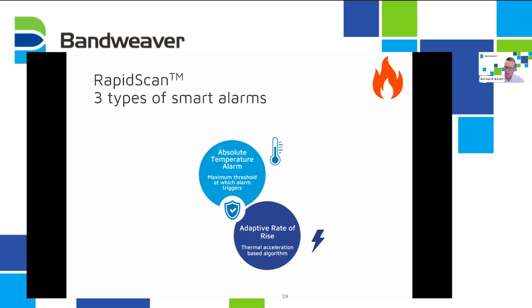We have our adaptive rate of rise. Other systems do use rate of rise. Ours, as we'll look into, looks at the baseline. It has an algorithm that looks at the change in the thermal situation and responds accordingly, which allows it to react very quickly, but again, not to create false alarms with slow moving detections. And finally, we have a hotspot detection, where it measures the deviation from the average temperature in the zone, which can be very useful in very slow developing fires, where it would fall under the radar of the adaptive rate of rise.